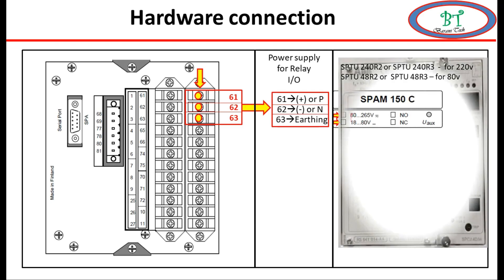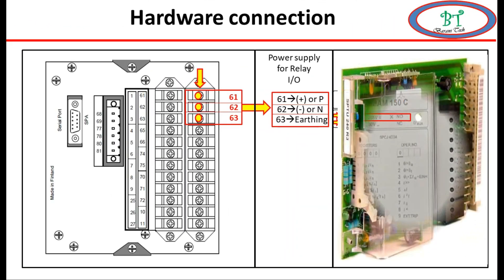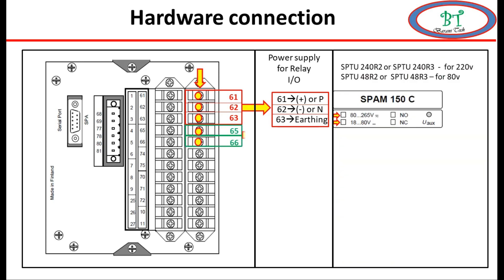If we need to check easily, the voltage will be marked on the front side of the relay. But if you want to see it deeply and correctly, then you have to open the front cover of the relay. Inside, the card will have SPTU 240, which is for 220 volt. If you have SPTU 48, then it has the indication for 80 volt. By seeing this we determine the correct power supply for the relay.